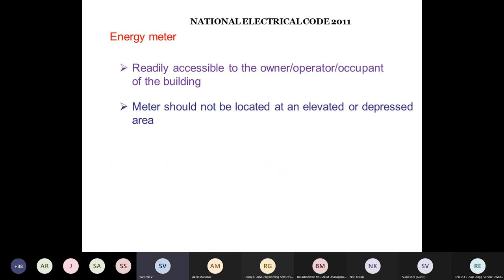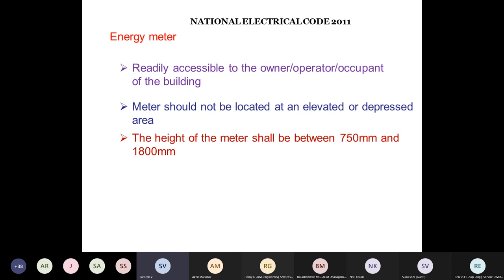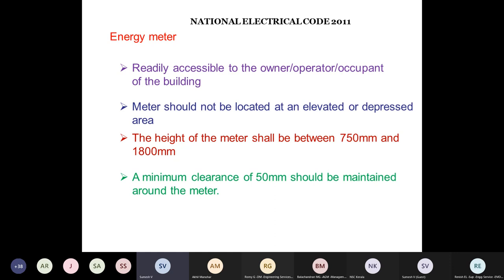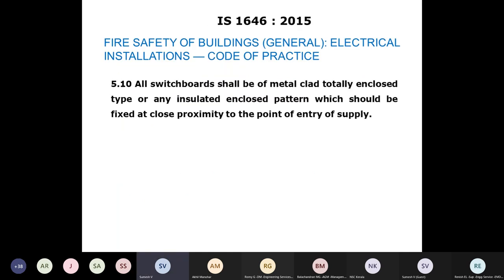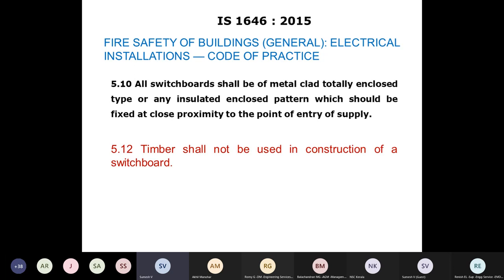These are clauses from NEC regarding the energy meter. It should be readily accessible, as we already discussed. It should not be located at an elevated or depressed area. Then the height of the meter shall be between 750 and 1800 mm. A minimum clearance of 50 mm should be maintained around the meter inside the panel. Then regarding fire safety, IS 1646 says all switchboards shall be of metal clad, totally enclosed type, or any insulated enclosed pattern. They should be fixed in close proximity to the point of entry of supply.